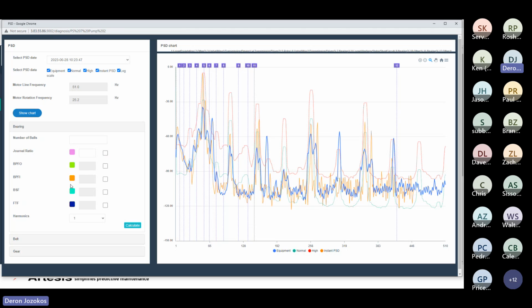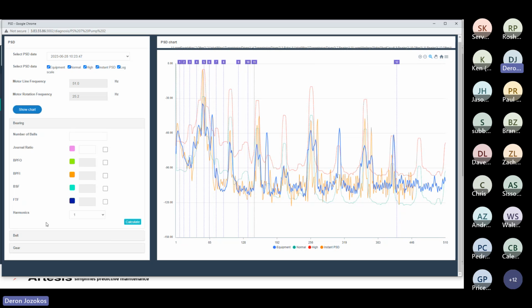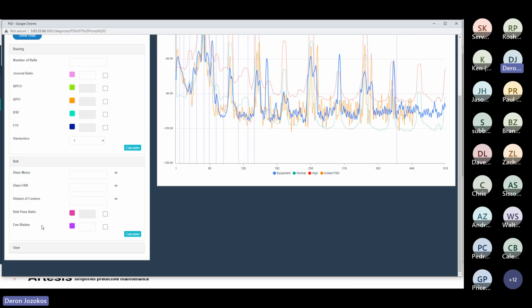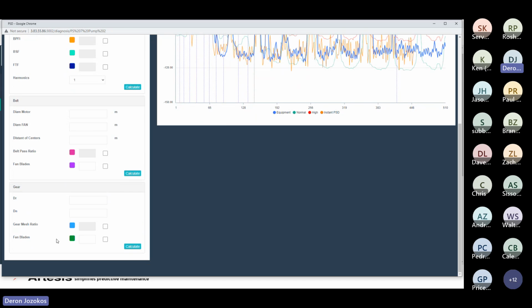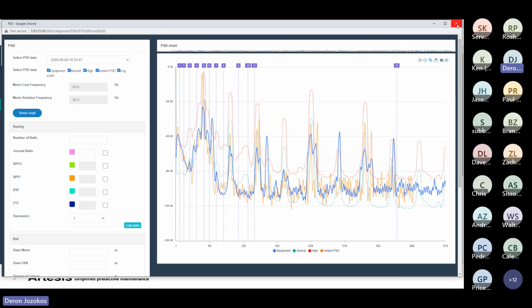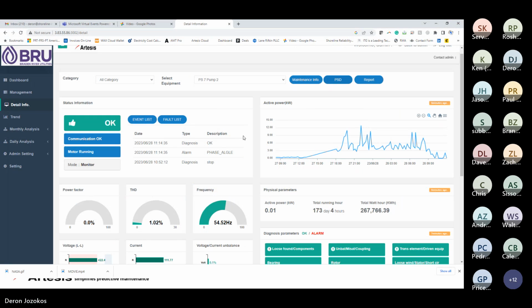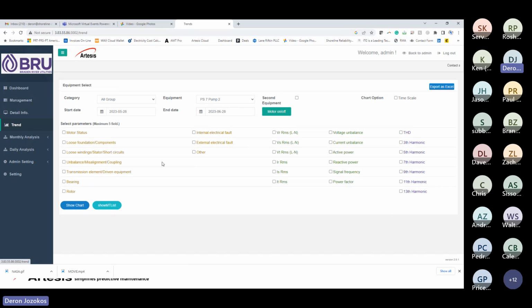Okay, if we had the bearing numbers installed here, like on the AMT Pro, we could plot out all the different fault frequencies. We can also enter in the belt information, get blade pass frequencies, and gearbox mesh ratios, blade pass, impeller blades, those types of frequencies. So you can do some advanced analysis, and we do offer two-day certification classes. The trending page here, I like to add in a quick case study. Whoops, where did it go? So the trending page, you can compare one machine to another. And there we go.